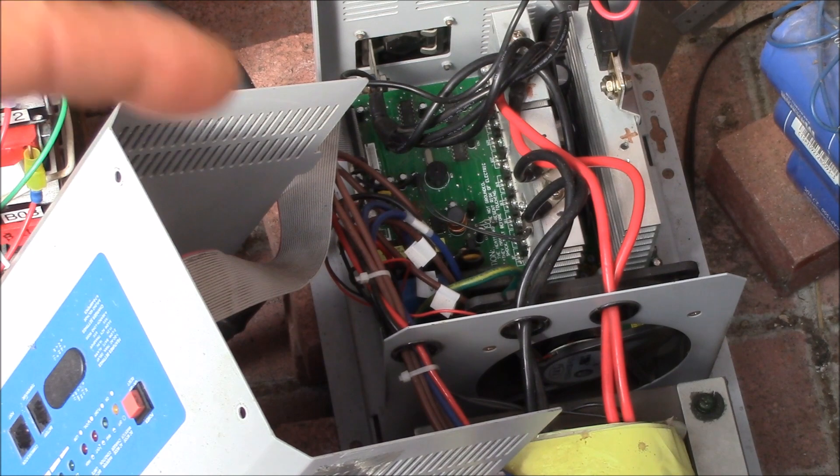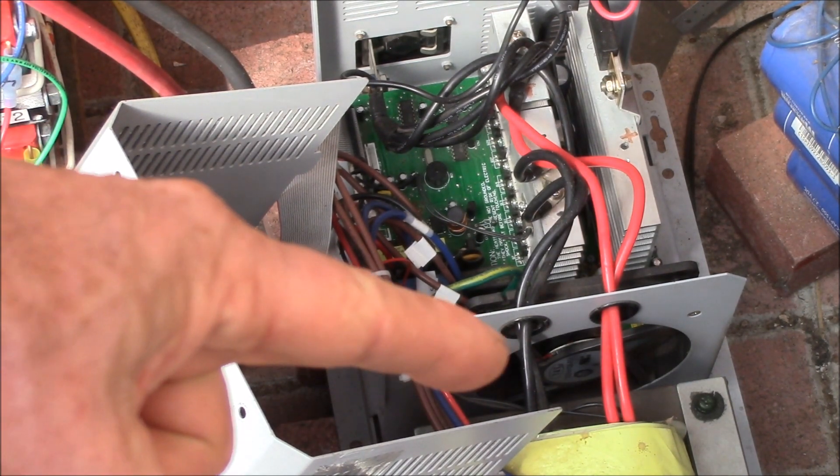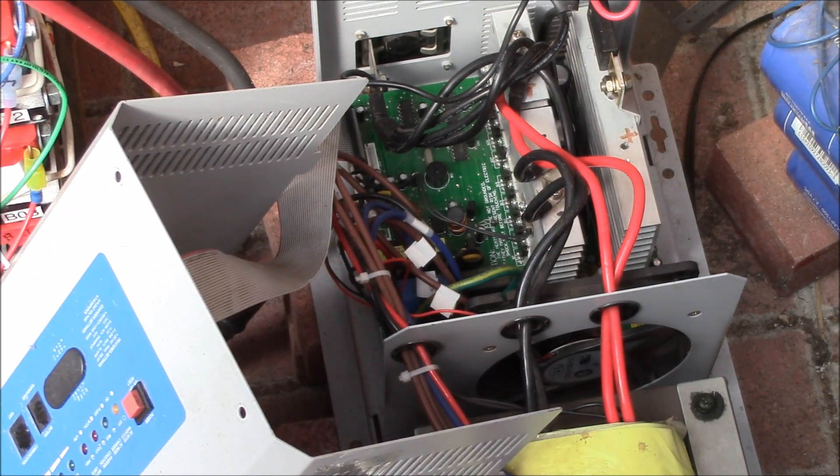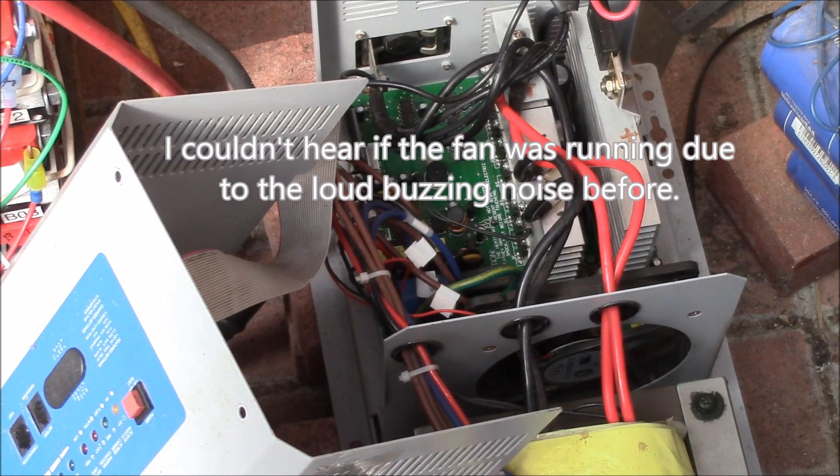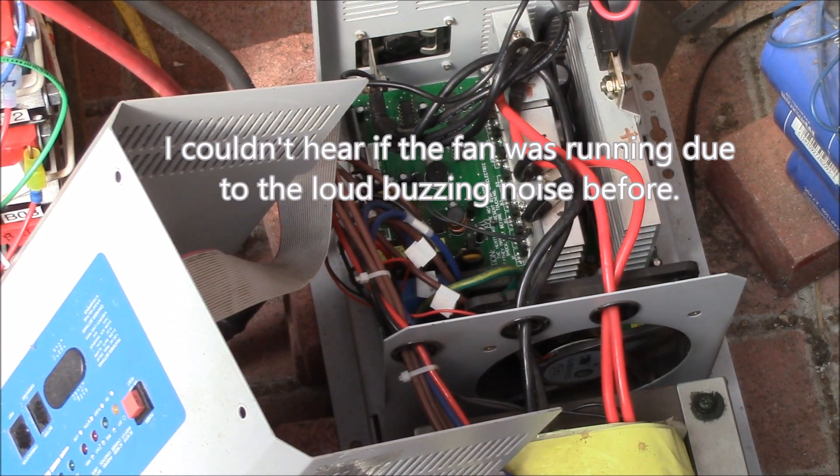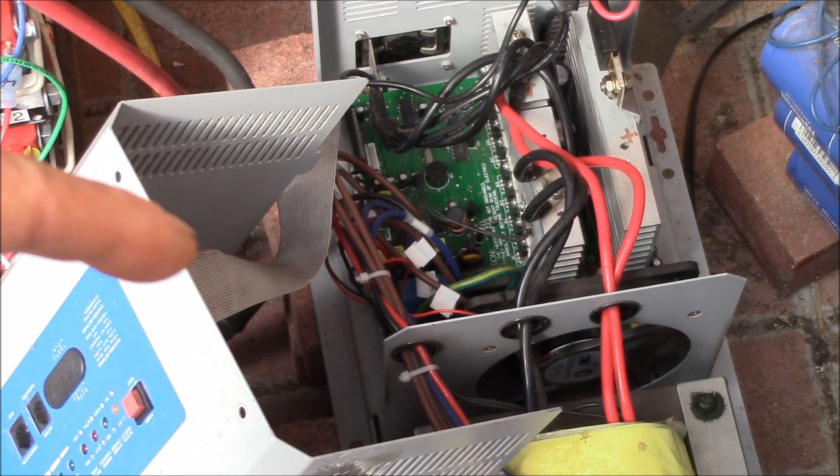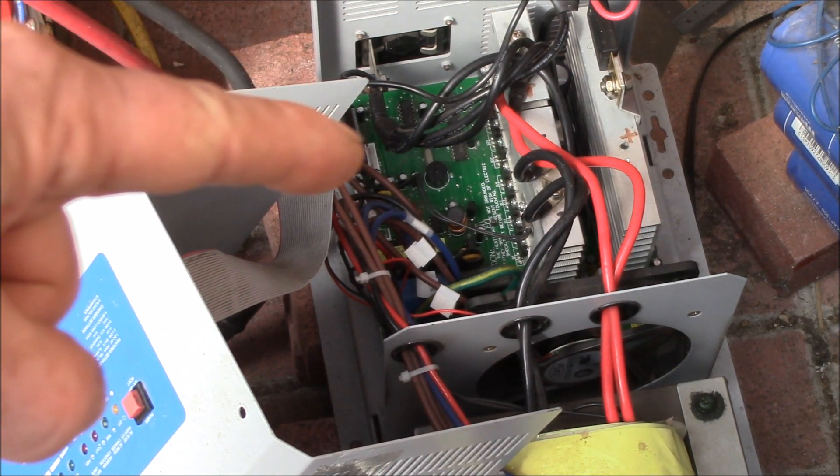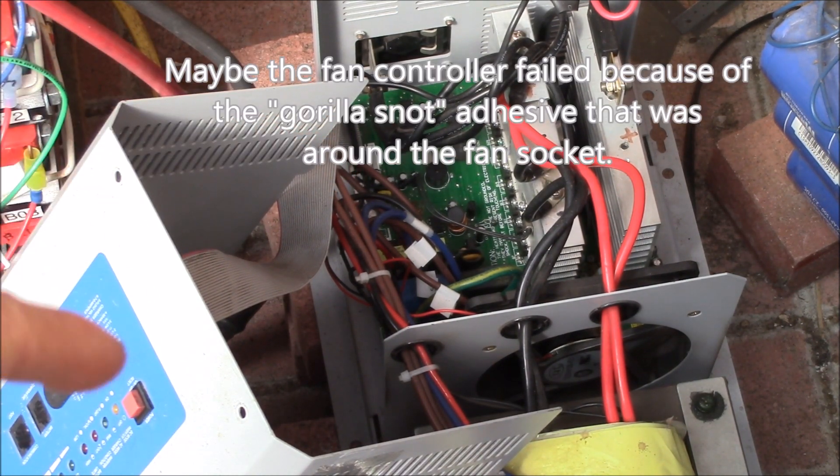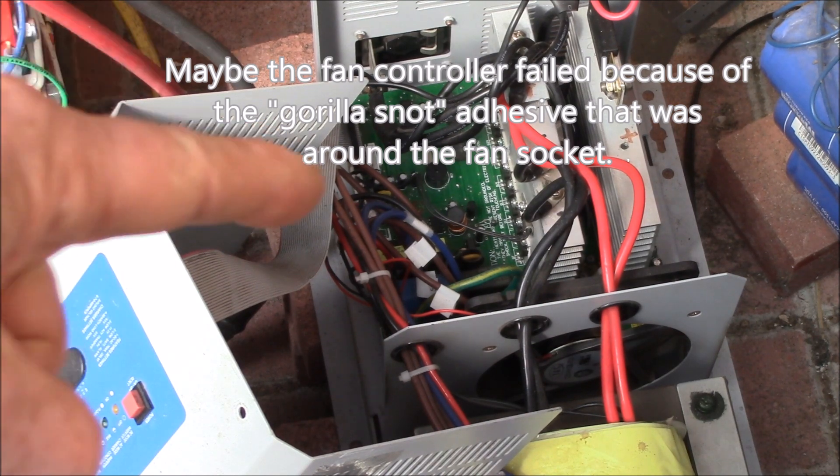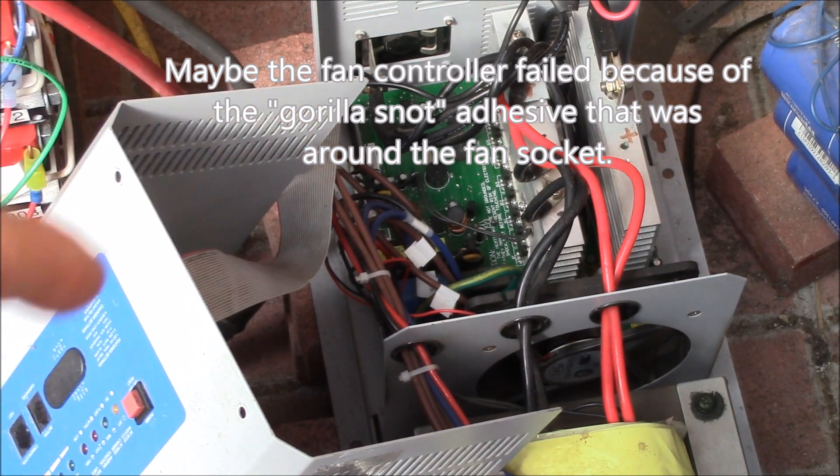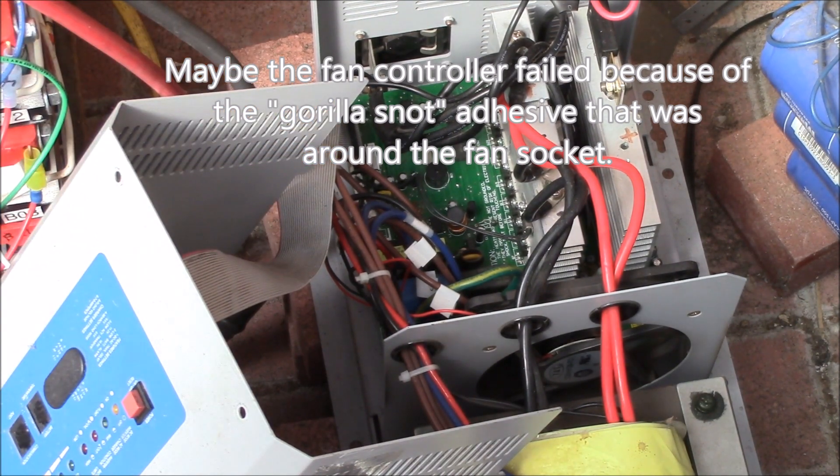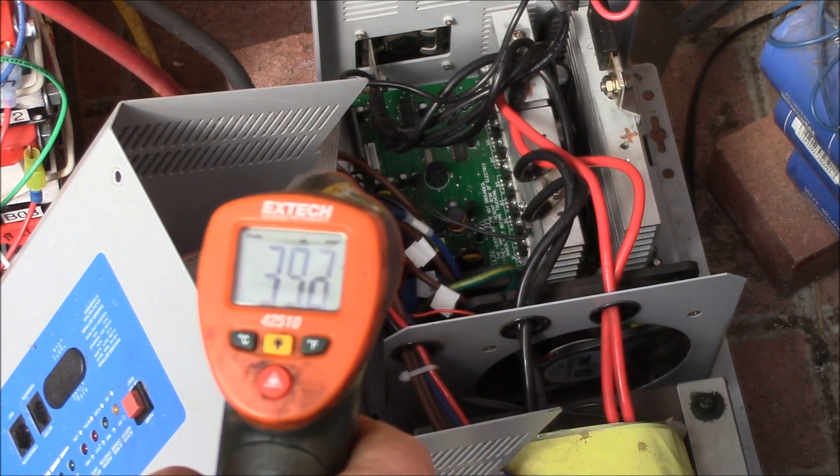You might notice that fan right there is not running. For some reason it seems like the fan controller in here quit working. I'm not sure if it failed when the capacitors failed or if the fan controller failed and that caused the capacitors to overheat and fail.